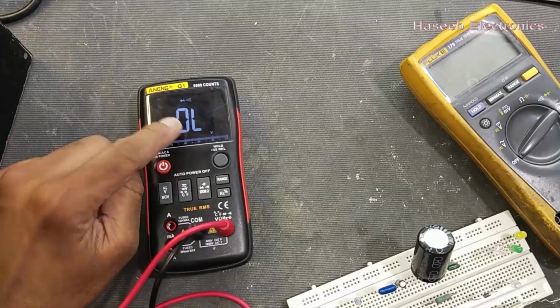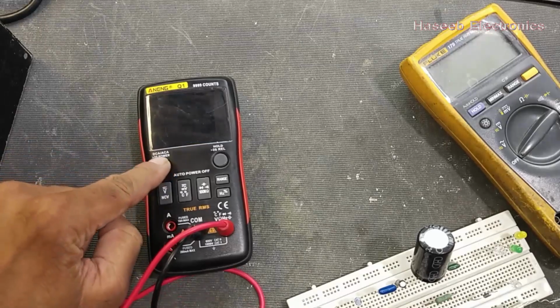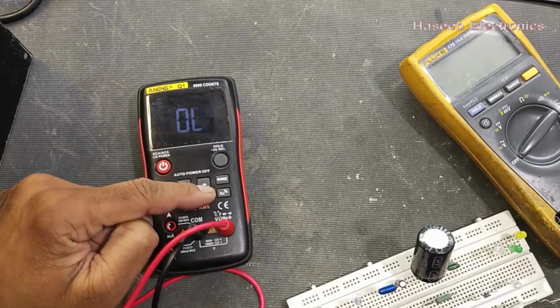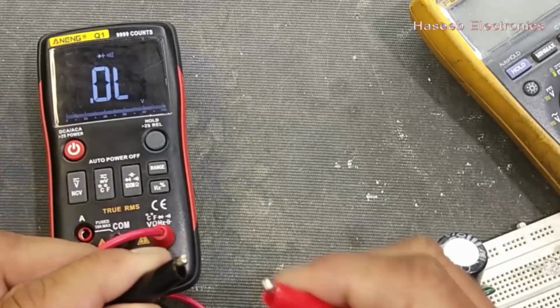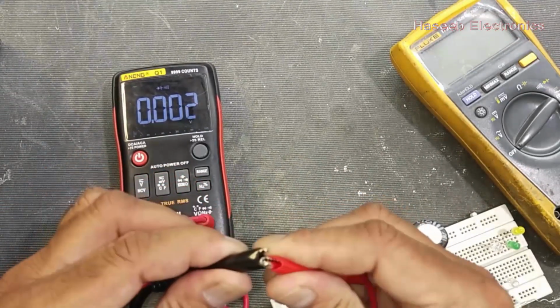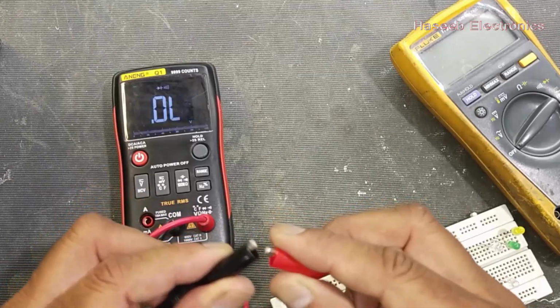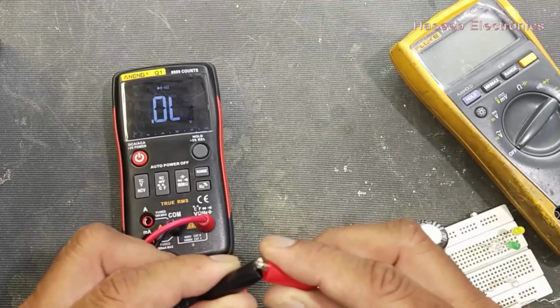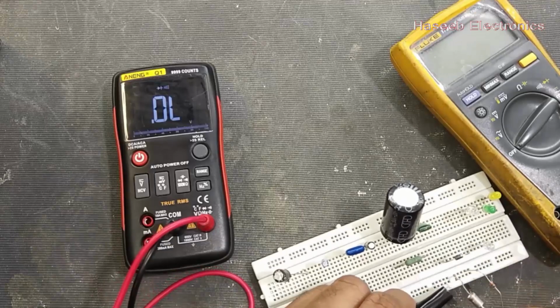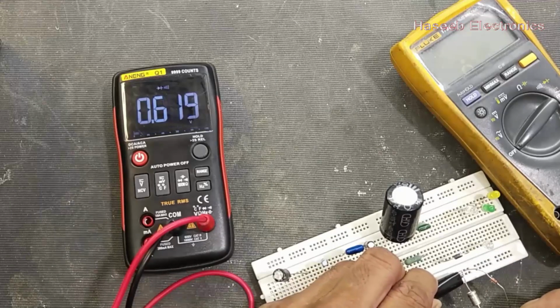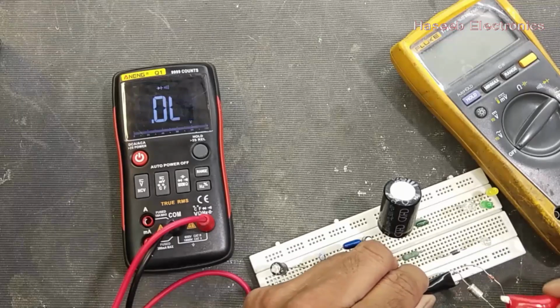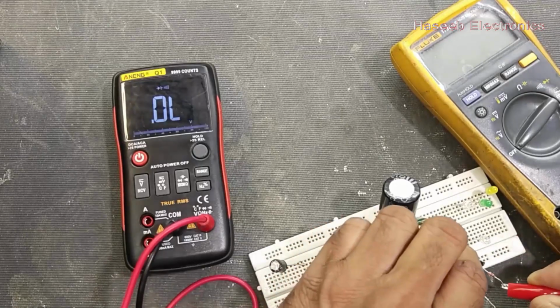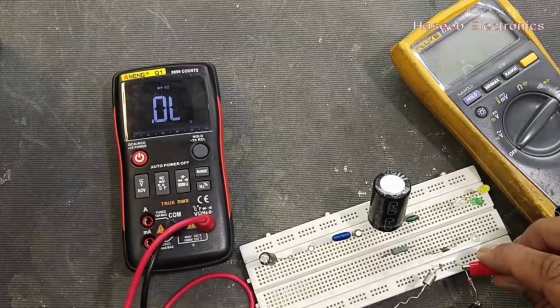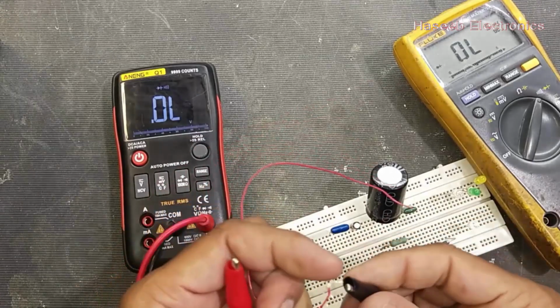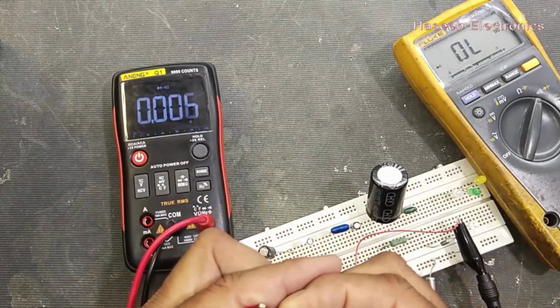The next, it is continuity. To test continuity, power on, move to diode and continuity by pressing this button. Now we are in continuity mode. We can test the buzzer. We can test diodes. At the same point, it is giving 0.6 volt. Open, open, 0.7 volts. For example, we have to test this wire. We can check continuity, so it will give continuity.